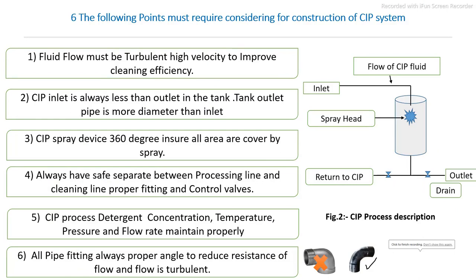The main points to consider for a typical CIP system in food processing are: whatever detergents or water flow into the processing line must be at high velocity — that means turbulent flow — which improves cleaning efficiency. The CIP inlet must always be less than the outlet in the tank, meaning the drainage system must have very high capacity compared to the inlet. The CIP spray system must completely cover all inside areas of the processing vessel.